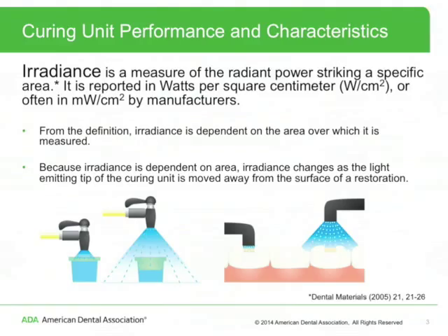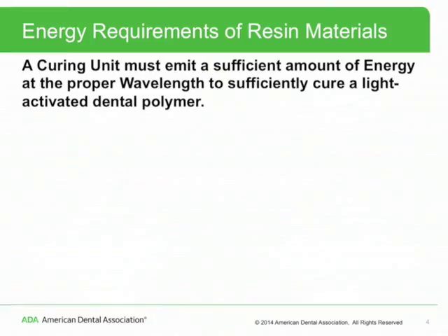However, as the curing tip is moved away from the restoration, less of the light strikes the restoration. In the illustration, we place the detector on top of the teeth to collect all of the light, and we remember that irradiance is power incident on a specific area. The measured irradiance will decrease as it is moved away from the surface of the tooth, because the power stays the same but the area that the power strikes becomes larger. A curing unit must emit a sufficient amount of energy at the proper wavelength to sufficiently cure a light-activated dental polymer.